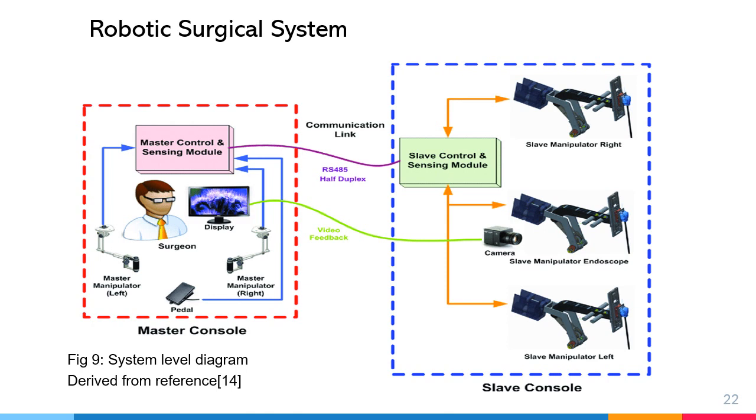The main reason for choosing the RS-485 bus standard is the fact that it is one of the most widely used communication highways in industrial and instrumentation applications. Thus, the differential transmission ability of RS-485 increases noise immunity and ensures a reliable link. The long-distance bidirectional communication over a single pair of twisted cables makes it more feasible.